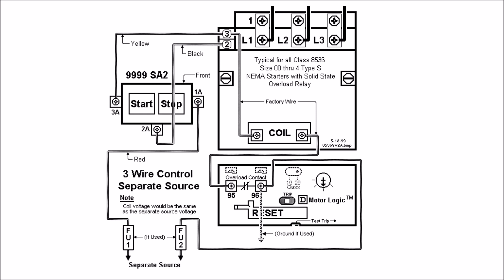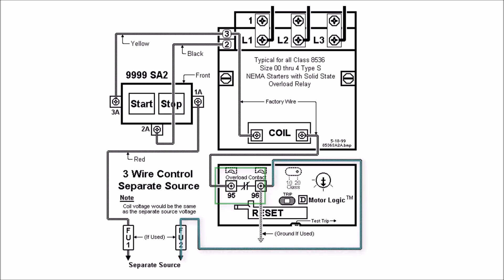For separate source your neutral will be wired directly to your overload relay which has a normally closed contact which indicates a trip when it's open breaking that circuit to the right-hand side of your coil.